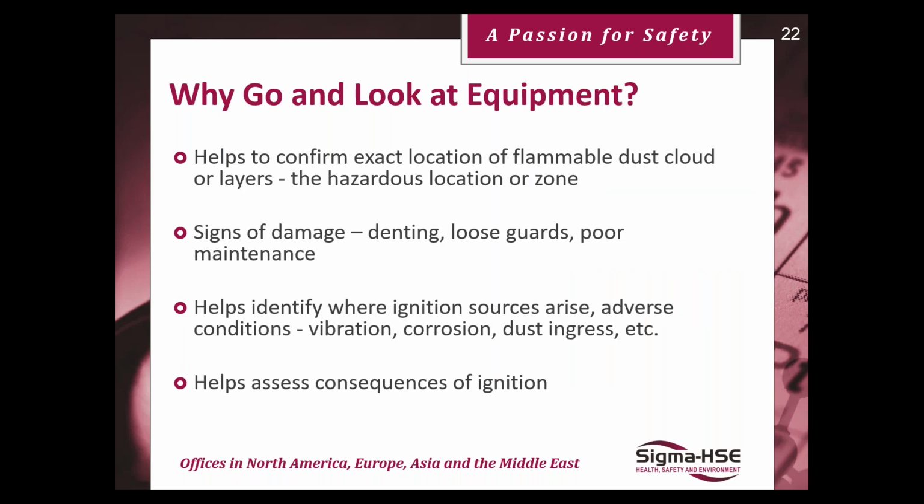So as I mentioned, why go look at the equipment? I think there's a lot of points out there, but yes, signs of damage, loose guards. Sometimes when you go look at it, it may be different from what you may see in the manual or the equipment drawings. So there might be modifications. It's just better to capture it. Maybe some ingress systems are not in place and not maintained as efficiently. And again, yes, it helps assess the consequences of ignition.